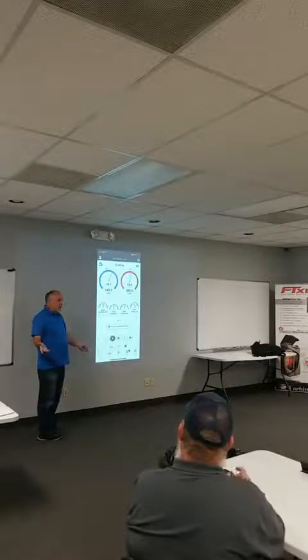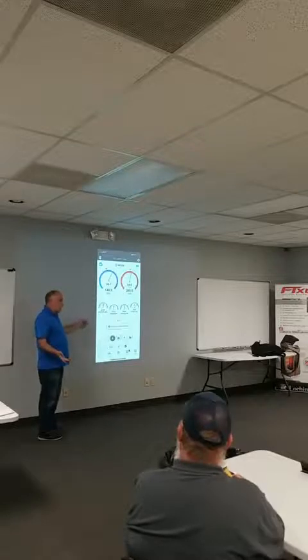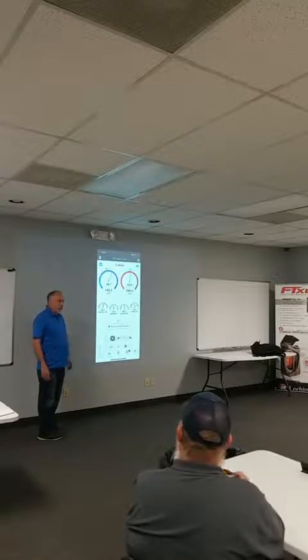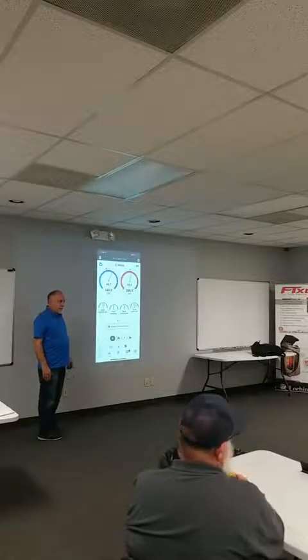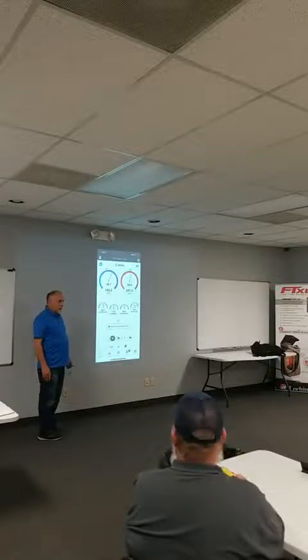It's just high suction pressure, right? It's got normal head pressure. Its head pressure is not low. It's not a compressor valve problem. It's because the airflow is that high, right? Well, with no ductwork on it. No ductwork. Yeah. You're gonna have more.